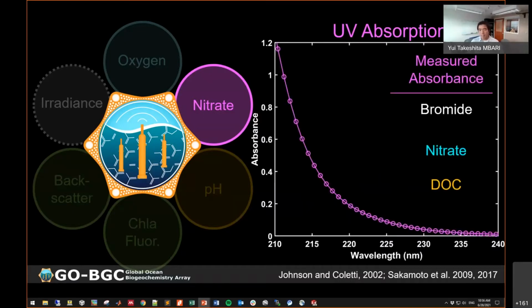The trick really here is how to deconvolute these three spectra, so you can subtract out what the nitrate concentration is. The approach that we take is to calculate what the bromide spectra should be based on temperature, salinity, and pressure data. Then you can subtract that out from the measured absorbance, and now you only have to fit two parameters, which is much more accurate.